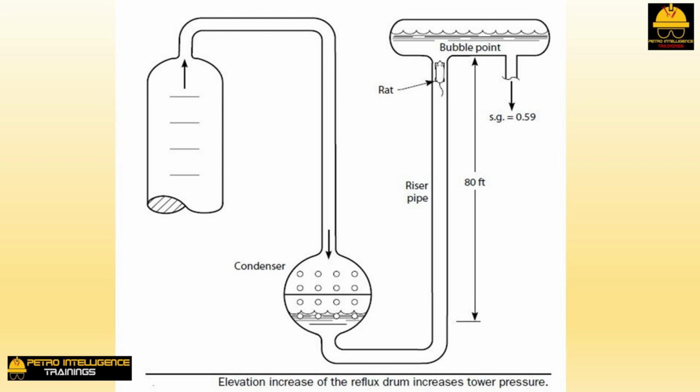The small increase in pressure in the reflux drum would push up the liquid level in the condenser. The surface area of the condenser available to subcool the liquid would increase. The liquid temperature would be reduced. As the subcooled liquid flowed across the dead rat, its pressure would drop. The liquid's pressure would fall to exactly that pressure that corresponds to the vapor pressure of the butane at the temperature in the reflux drum.